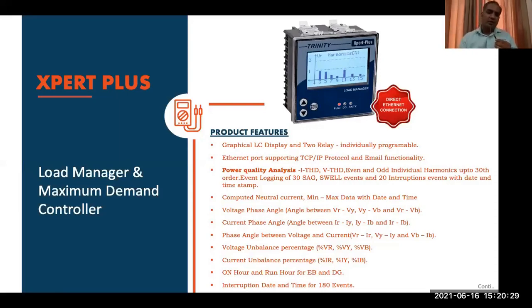So when I talk of SAG and swell in generalized terms, suppose my current running voltage is 240 volts, and I define a sag event as a 10% drop in voltage, or a 20% drop in voltage. I can define from 10 to 90%. So when I say a 10% drop in voltage becomes a sag event for me, whenever my voltage drops from 240 volts minus 10%, the event shall be recorded in the meter's memory along with date and time.